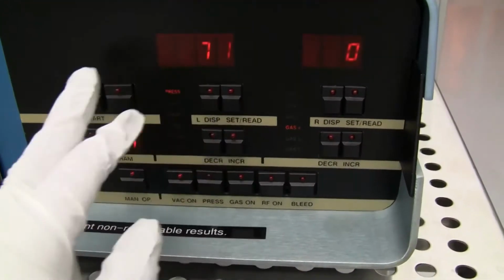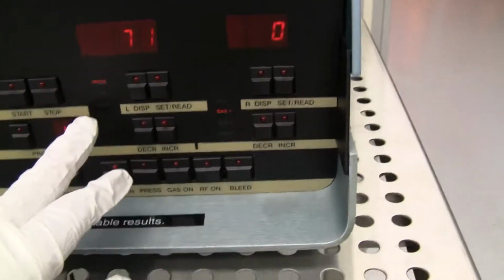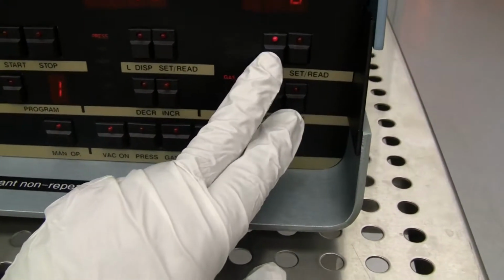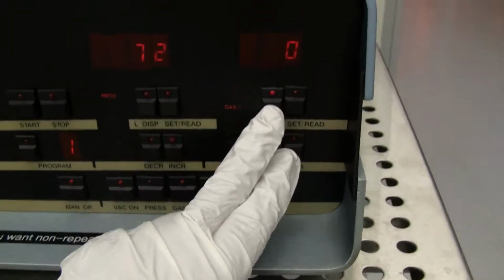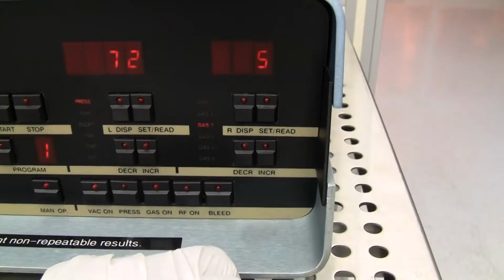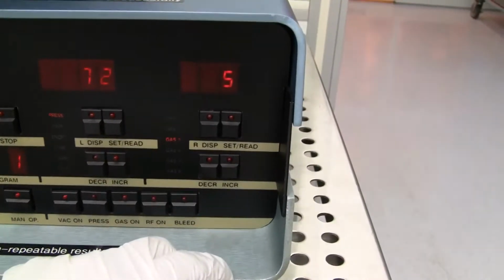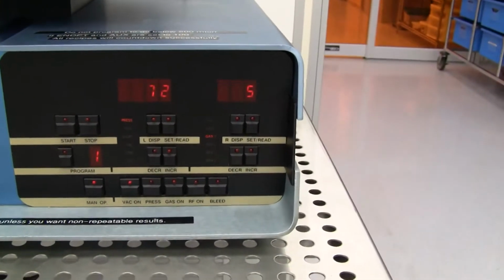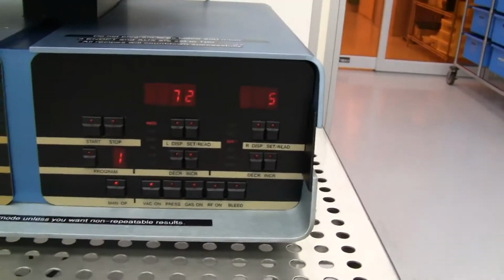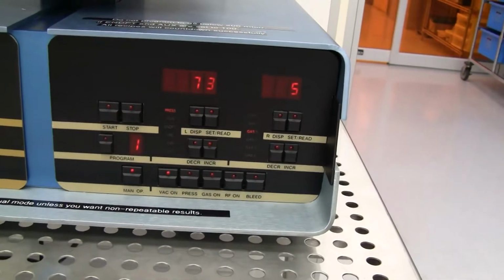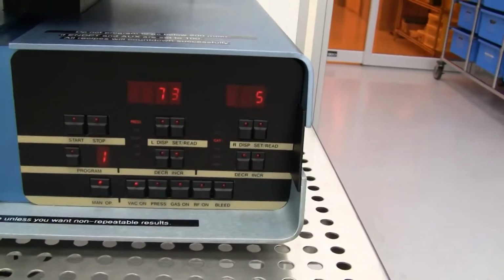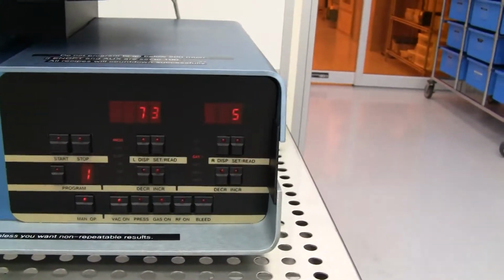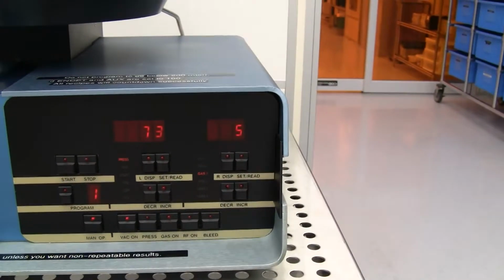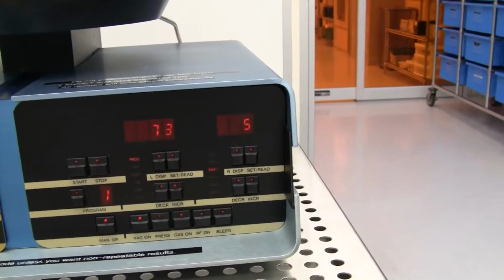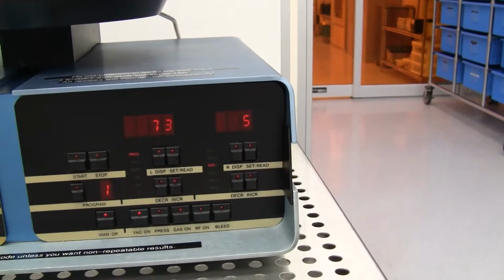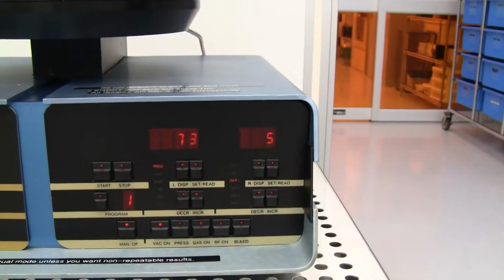I don't know. Looks like everything's okay, other than that mass flow being not correct. Well, now it's up to 5. So one of the other engineers reported that even when you close the valve in the back for this gas line, it still reads 5. So it doesn't seem to be leaking. It does really appear to be a calibration issue. Alright, guess I'll do a couple more diagnostics and see what I can learn about zeroing these meters out.